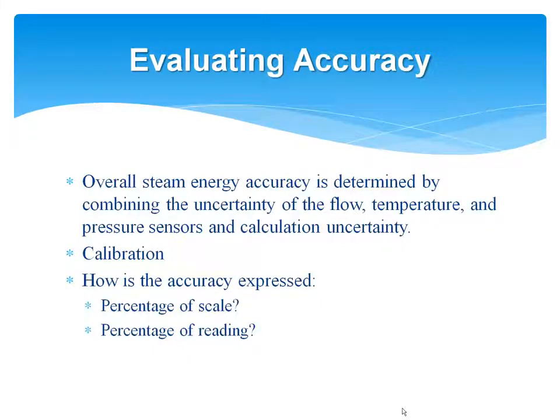Accuracy is obviously another very, very important side of the measurement. The overall steam accuracy is really going to be a function of the combination of the three measurements that we saw we needed to take earlier, along with the calculation uncertainty. One of the tough things, especially for users and engineers, is that overall number is rarely published in manufacturers' literature. And so that requires the engineer and user to go out there and do some digging and some calculations in order to make sure that they're getting what they need in terms of overall accuracy. This is obviously an area where some standardization would help tremendously in being able to baseline a certain performance level.